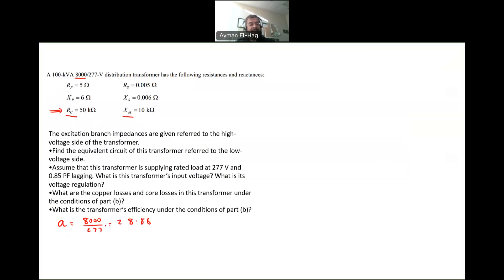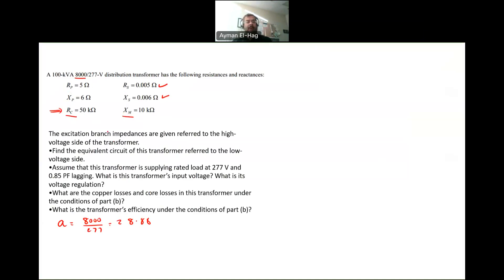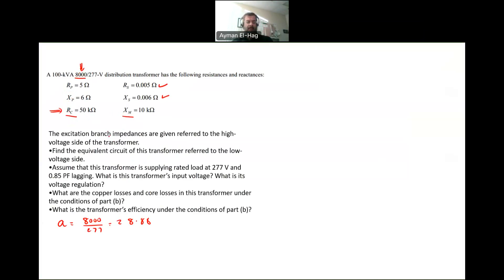The question says I want the equivalent circuit referred to the low voltage side of the transformer. RS and XS are the resistance and the leakage reactance of the low voltage side, so no conversion is needed — they're already given their final values. What I need to convert is RP, XP, RC, and XM, because RP and XP are the primary values referred to the high voltage side, and RC and XM, as mentioned in the question, were also taken referred to the high voltage side.